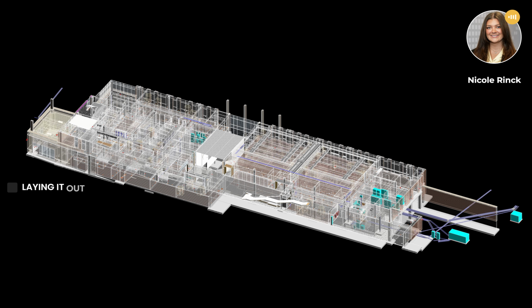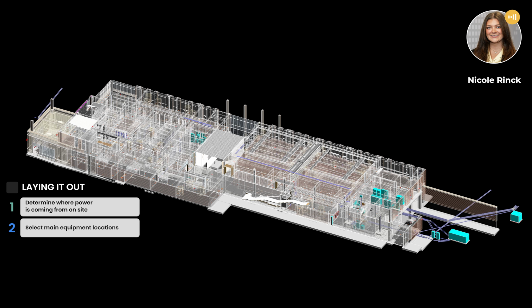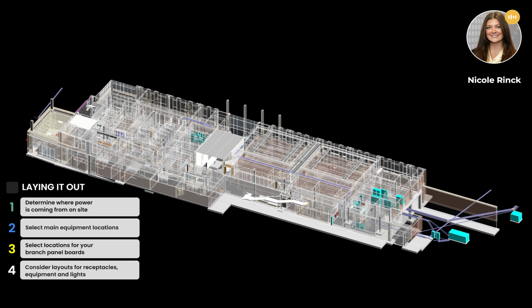To review, the steps are: 1. Determine where power is coming from on-site. 2. Select main equipment locations for the transformer and switchboard. 3. Select locations for your branch panel boards. And 4. Consider layouts for receptacles, equipment, and lights. Good luck on your electrical system design.